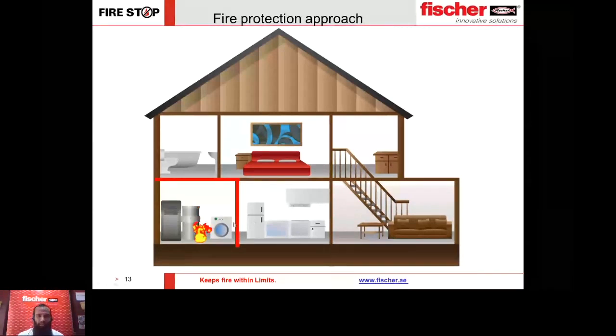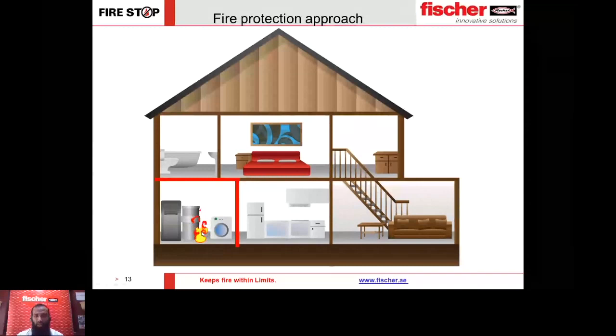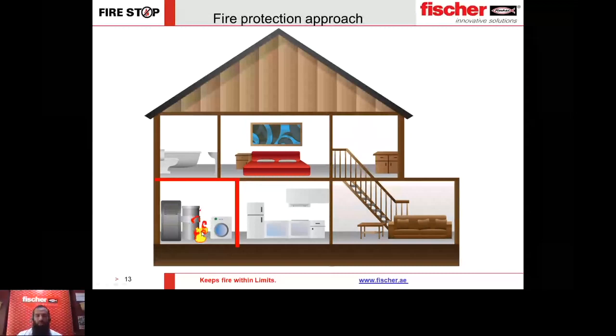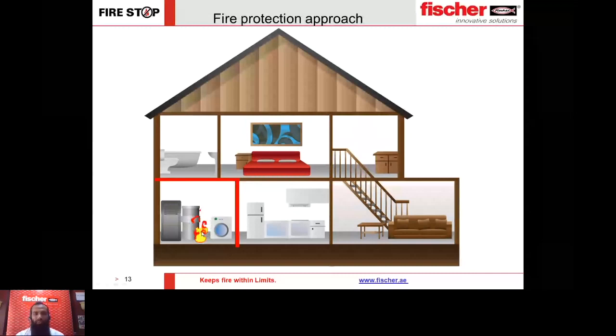Let me now introduce the concept of fire rating. Generally the fire rating belongs to the fire barrier itself. If a barrier has a rating of two hours, it means it should contain fire on the fire side for up to two hours — it should not allow smoke, toxic gases, or flames to pass through. Now imagine on a project somebody constructs a two-hour rated fire barrier, and then an MEP contractor makes a large hole in that barrier.